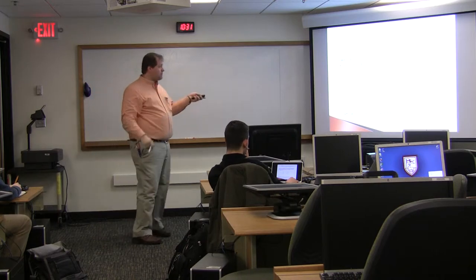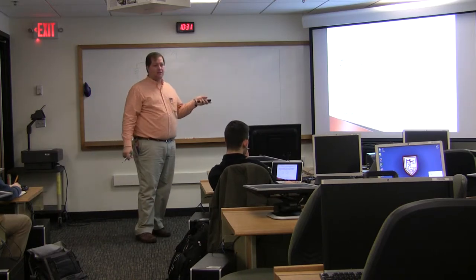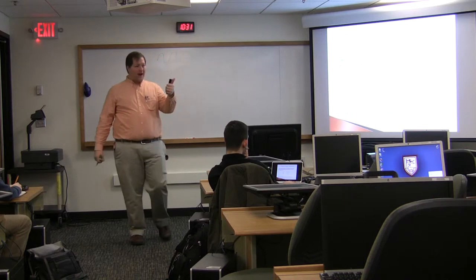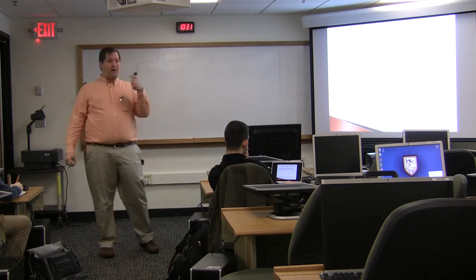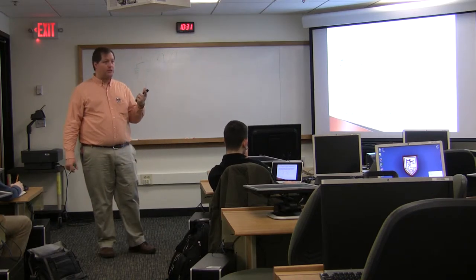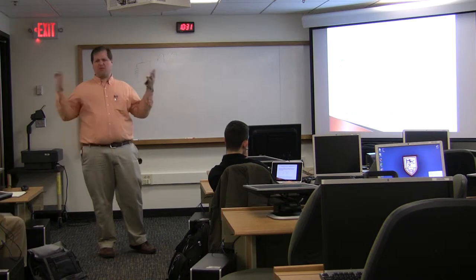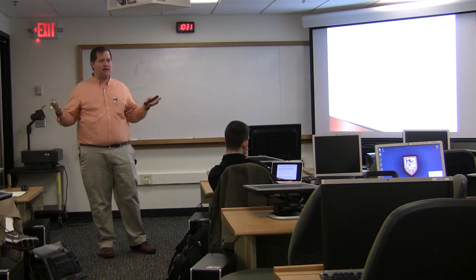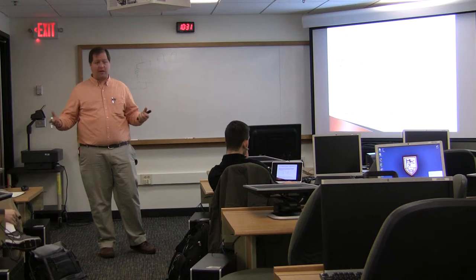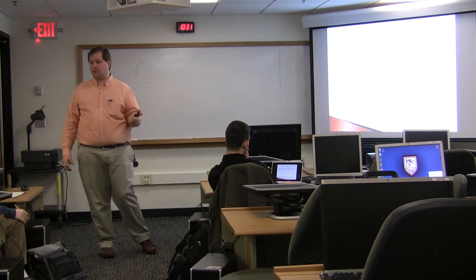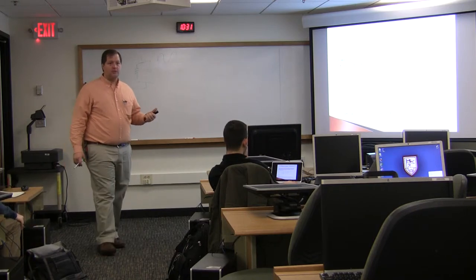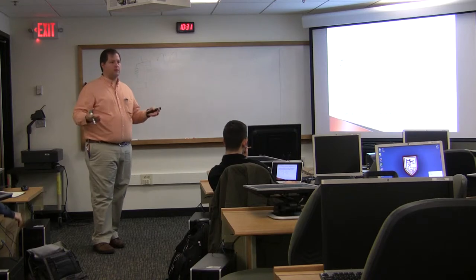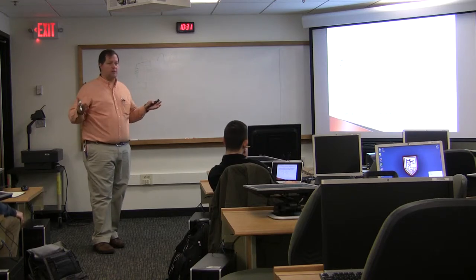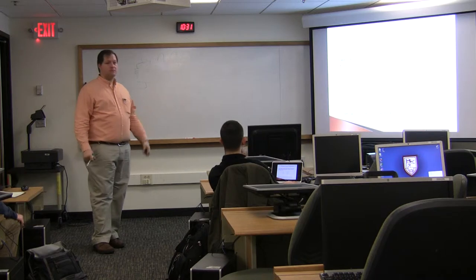That would mean you'd have to supply all that current, which means bigger wires and a lot more power available from your power company just to start the motor. But once it's running, you don't need it anymore — what a waste. You've spent a lot of extra money on heavy-duty wires and circuit breakers just for a momentary utilization, like a couple of cycles. So why not put a capacitor in?